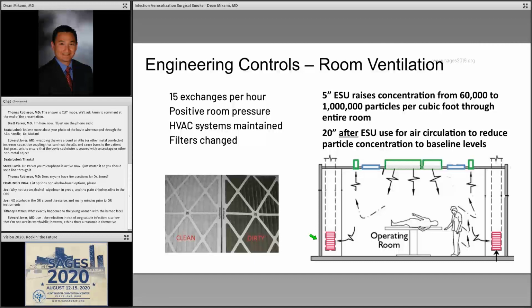So, if you have a patient that is high risk, that is maybe positive for COVID, or is a PUI, person under investigation, you should wait at least 4 to 8 to 12 minutes, so there are multiple air exchanges happening in the operating room before entering. So we know the use of electrosurgical units can raise the concentration of particles in the air from 60,000 to 1 million particles after 5 minutes of use. And 20 minutes after using that, the room can get cleared out by our whole room filters.